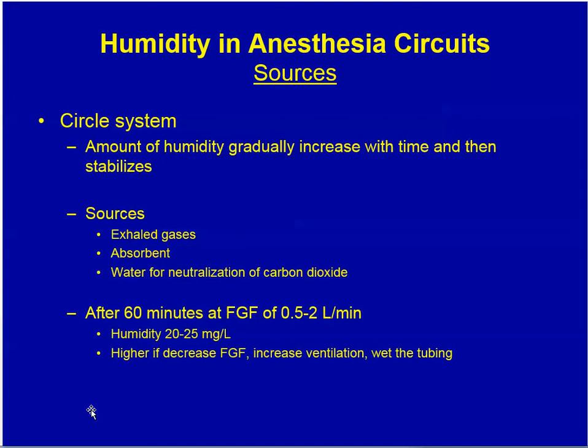Another source of humidity is the circle system, where humidity gradually increases over time. The sources of this humidity are the exhaled gases, the absorbent, and water from neutralization of carbon dioxide. After about 60 minutes at fresh gas flow under 2 liters, the humidity is up to about 20 to 25 milligrams per liter.